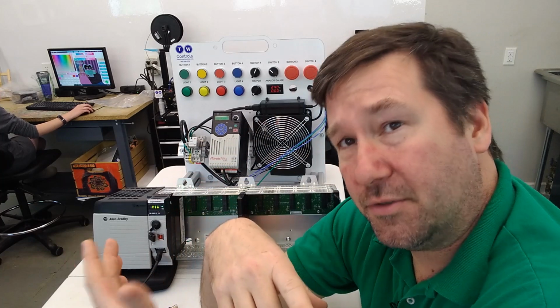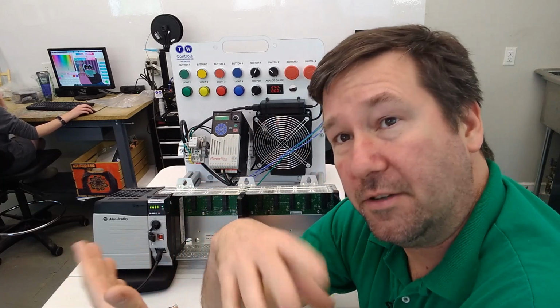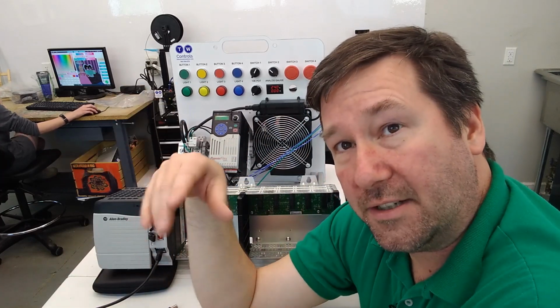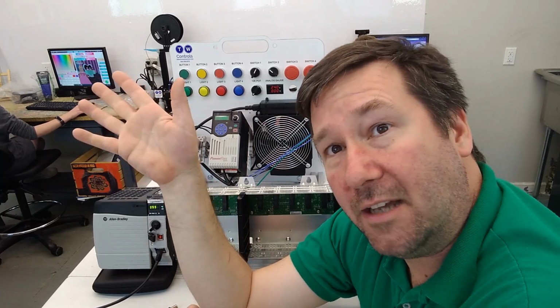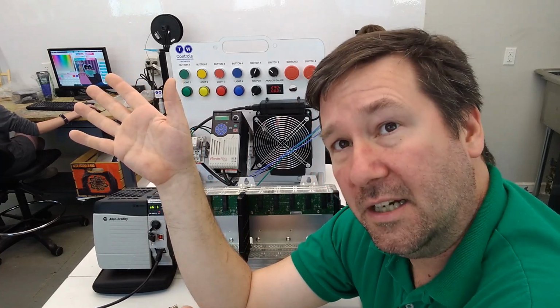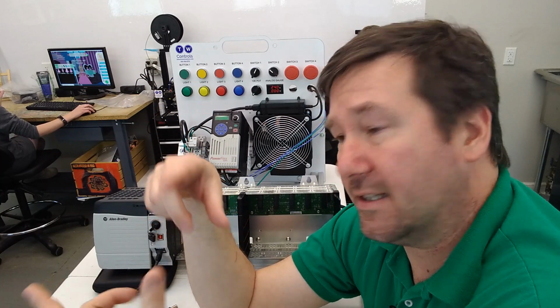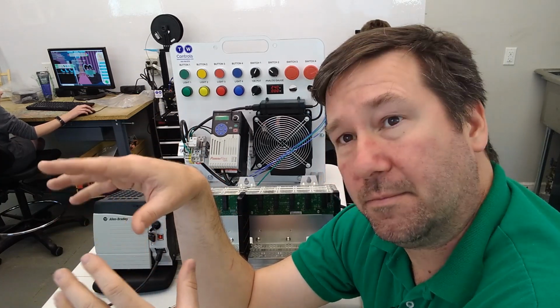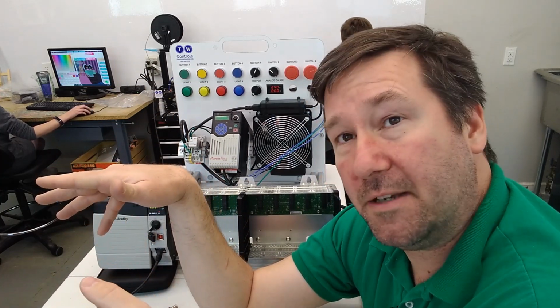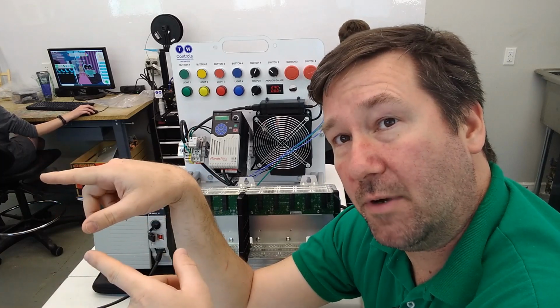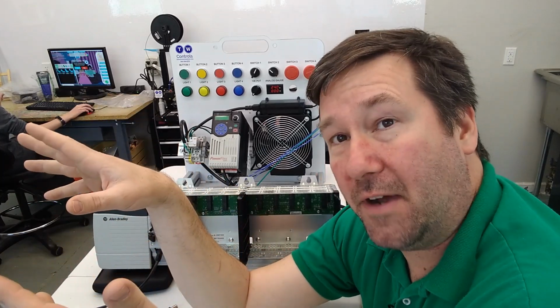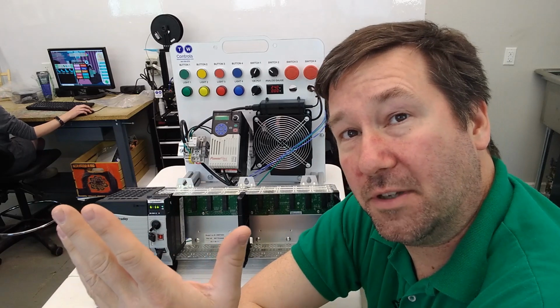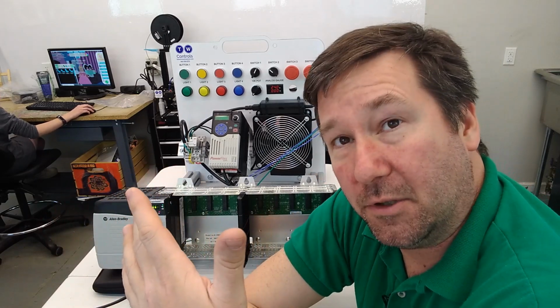When I went to do it in the traditional ways through Ethernet, USB, Who Active, hit the download button, it was grayed out both ways. So I found that when I opened Controlflash up, the upgrade seemed to be fine. So that's the route I went. And after that, everything worked fine. So I just wanted to share this video with you just in case you run into a similar problem.